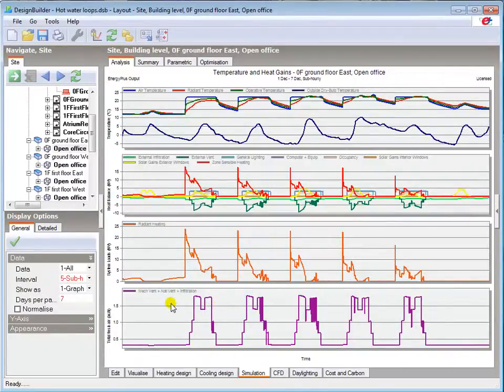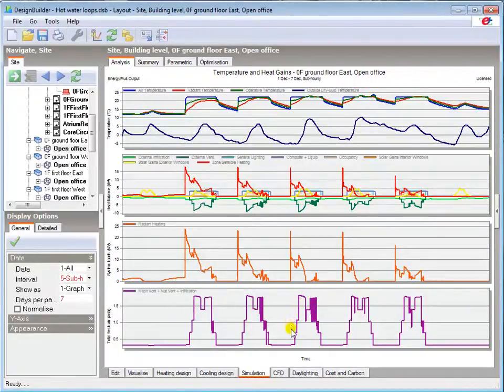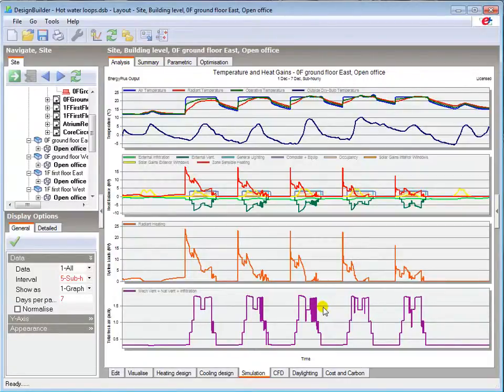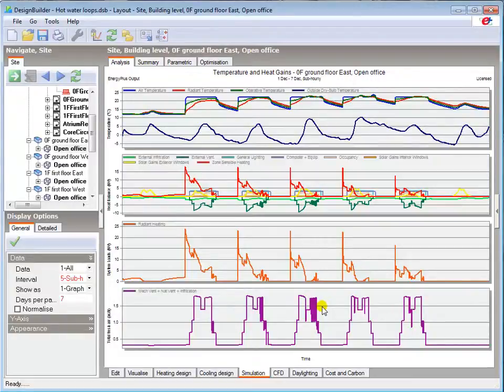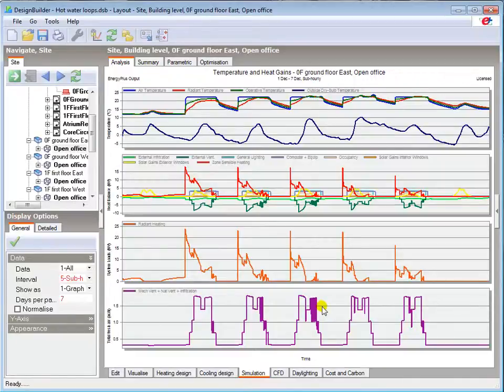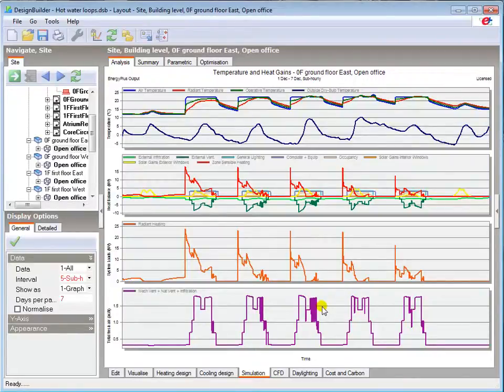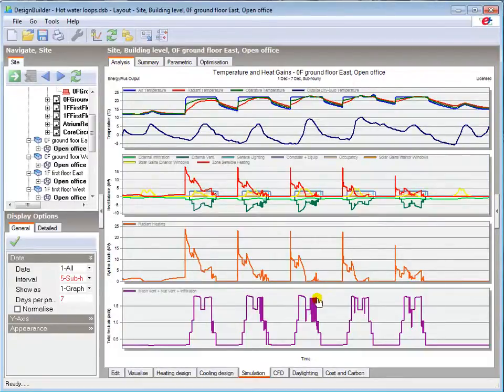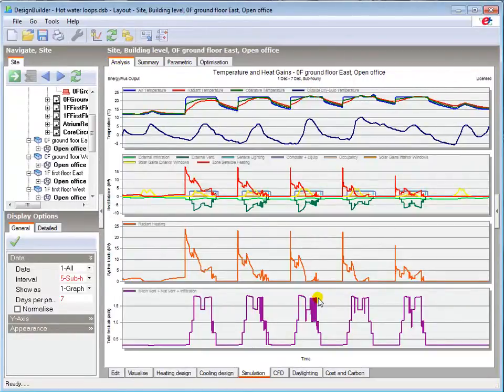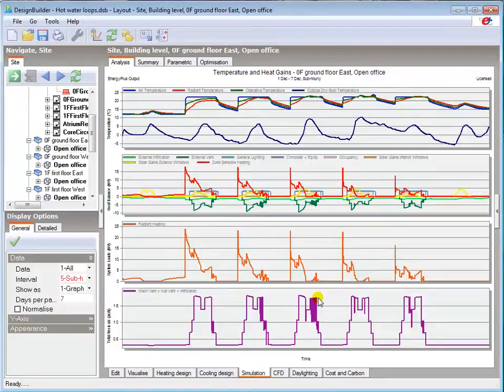The total fresh air profile shows that there is a degree of control action to limit the natural ventilation rate. This is because the default NatVent cooling setpoint is 22ºC, which is the same as the heating setpoint, and when the zone temperature is below the NatVent cooling setpoint temperature, it will switch off. With the heating system being controlled, there will be small variations in the zone temperature around the setpoint, which results in the instability you see here, with NatVent frequently cycling on and off. If you wish to avoid temperature control of natural ventilation, you should change the NatVent cooling setpoint to zero. NatVent will then always be provided according to the schedule, and the extra heating load will be reflected in your heating energy consumption results.